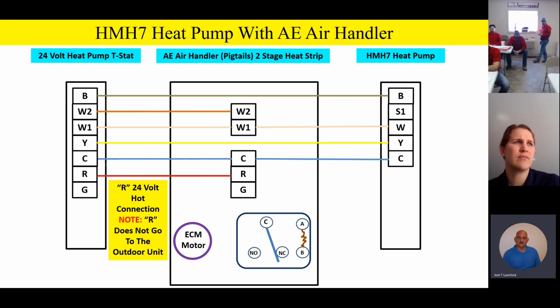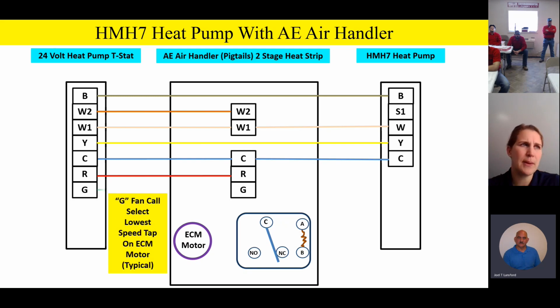R is 24 volt hot from the thermostat to the indoor unit. Now this is really important, guys. We do not take that R terminal, that 24 volts, outside, because the way the outdoor unit is configured and designed, it doesn't need 24 volts all the time from the indoor unit. So we do not take R outside. In addition, we don't take G outside. Obviously, that's just your fan wire, and that's pretty standard in the industry. G is your 24 volt fan connection from your thermostat to the indoor unit.